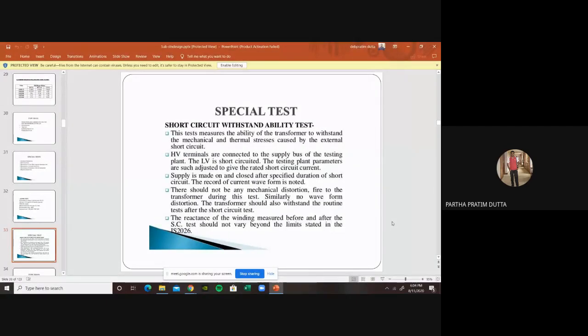So what we usually do: HV terminals are connected to the supply bus for the testing, and LV is short circuited. Test plant parameters are adjusted to give the rated short circuit current. Supply is made and closed over the specified duration of the short circuit, and the current wave is recorded. We see that there is no mechanical distortion or fire during this test, and no waveform distortion on the oscilloscope. We also see the reactance of the winding measured before and after the short circuit test, and whether it goes beyond the limit as per IS specification 2026.